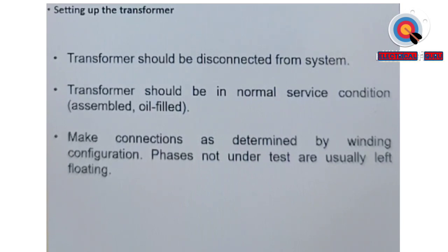The reason for that is we do not want the influence of any stray capacitance or any additional elements which have a capacitance or inductance value, because if those components get involved in the measurements, then the response will not be only of the transformer, but a combination of the total construction. So it is recommended that the transformer should be fully disconnected, and then only this test should be performed, so that you are checking the geometry of the transformer and the transformer alone, without the influence of any other component.